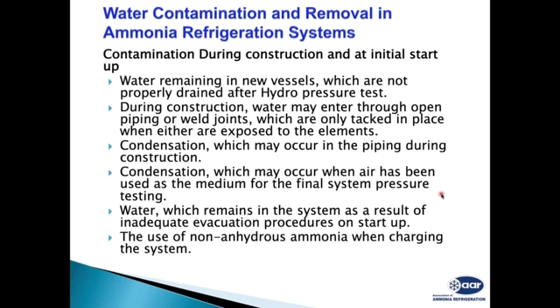When the plant is being constructed, many times people do hydro testing of the plant, vessels, and equipment, which is not correct. It should be done with dry nitrogen. Once you do hydro testing, it's very difficult to remove the water, and if this water is not properly removed, it will remain in the system.